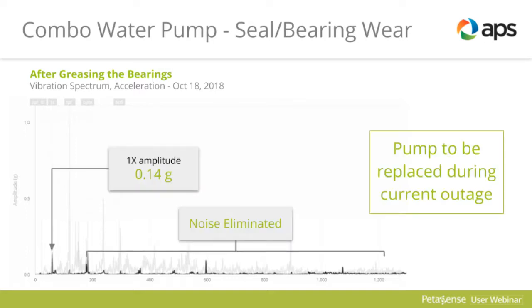During the outage, we replaced the pump, and we did an autopsy on the pump. We found out that the pump had filled with water, and that it had damaged the high-speed shaft, and there was also cavitation pitting on the impeller of the pump. All that we had seen basically with our spectrum readings. What we had said was actually what happened.